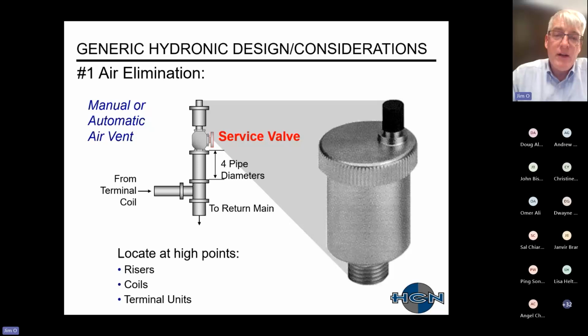And then I just want to point out that you should put a little service valve. I couldn't find a picture of it, but usually it's a little petcock. The automatic air vent works with a clapper, not that type of clapper. They periodically have to be cleaned out. So the service valve does its service by shutting off the water, sealing your water system, and then you can unscrew the little air vent that's shown here on this drawing. This drawing makes it look enormously big, but maybe it's 3 or 4 inches tall.